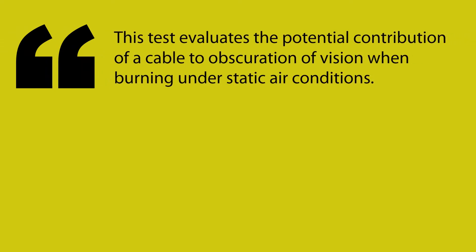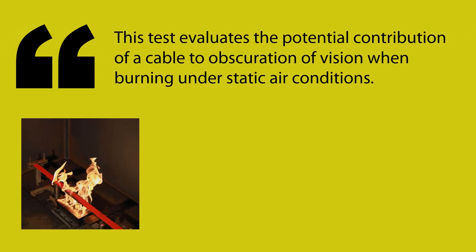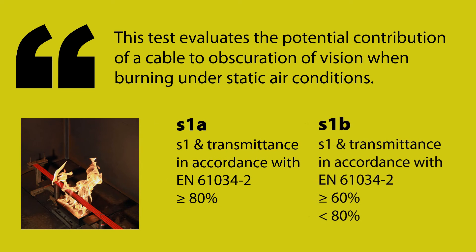To clear up any confusion: if you pass S1, you can then opt to add an additional test to establish what is termed transmittance. This test is not new to us and we've been using it for a number of years to qualify an LSOH cable. It is related to smoke opacity or density — effectively the amount of light that can be measured through the smoke produced. More than 80 percent is classified as S1a, between 60 and 80 percent it is S1b, and below 60 percent it is a fail, which could actually impact upon the claimed S1 rating.